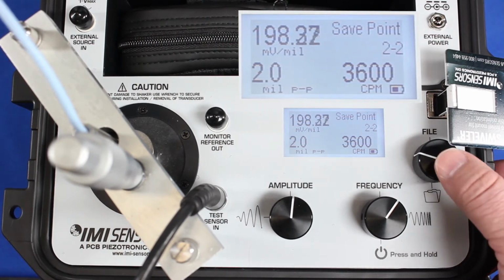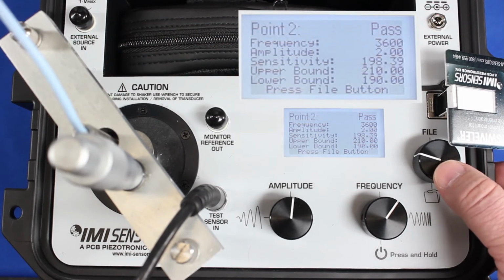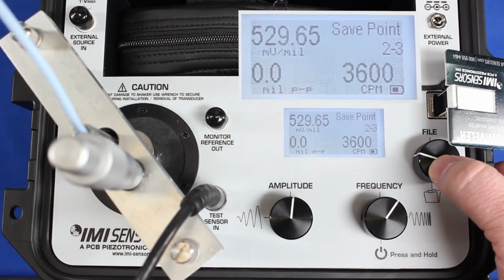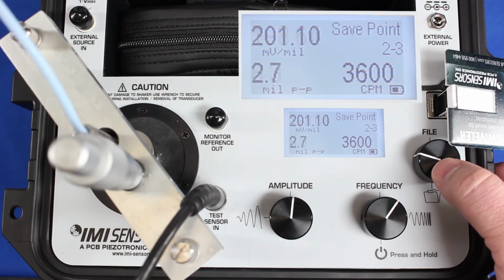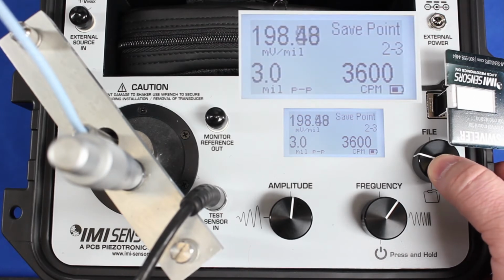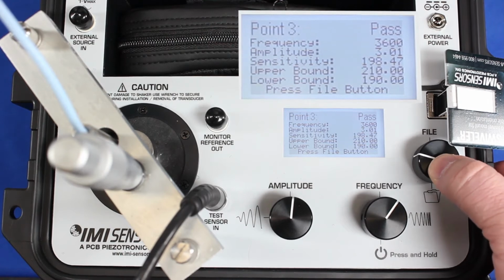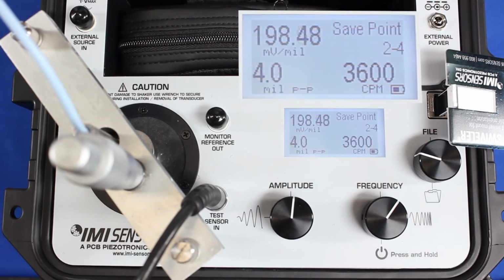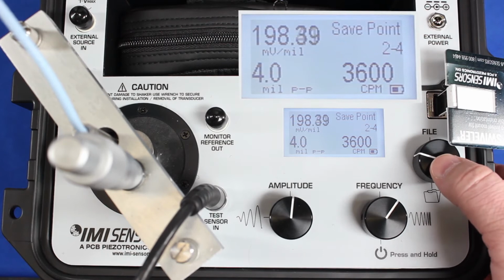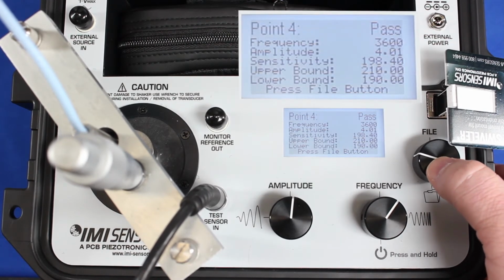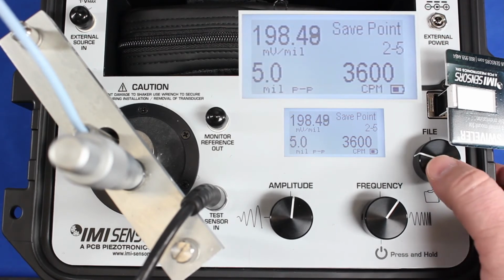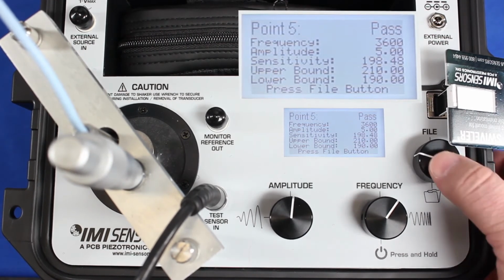And now I can move very quickly through the test, 2 mils peak to peak, 3600 CPM, press the file button again, and I'm notified that the sensor passes. The next test point is 3 mils peak to peak at 3600 CPM, and I get a pass notification again. At 4 mils peak to peak, this is where I may have my vibration alert, or even a lower level perhaps. So if I'm teed off of the calibrator, I can make sure that the vibration alert in the monitoring system triggers as well while I create my calibration certificate. And again, I pass. 5 mils, pass again.